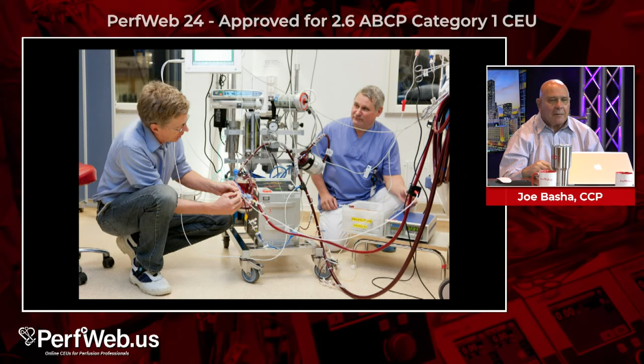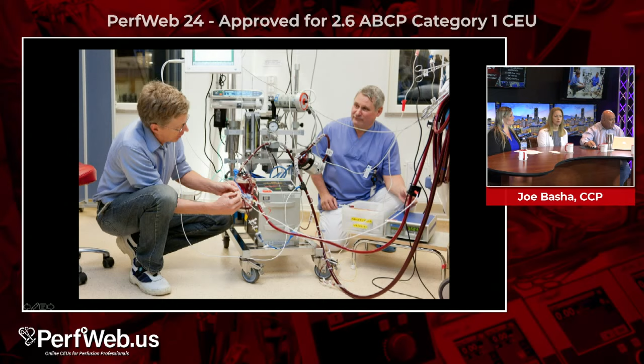So you have this here. The venous line's coming down, here it's on the floor, and here's one of these pigtails with a stopcock and a syringe. Now, it's good they have the little pigtail attached to it, which is good, but if this thing opens up, this line right here is under, as I said, tremendous negative pressure. Now, he's got a syringe on it to try to block it right there, but if somebody steps on it and cracks it, and don't tell me it can't happen. If the patient's family comes in there and hasn't seen this patient yet and is frightened to death and wants to get up there close to them, that can happen. Again, it may be a very good circuit. It may work very, very well. I've never really understood why everybody wants it on the ground like this, but they do it supposedly for air. I don't think it makes any sense. But regardless, this system here, again, may be a good circuit, but it's not done in a way that I would advocate for.